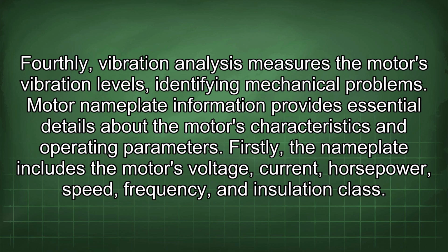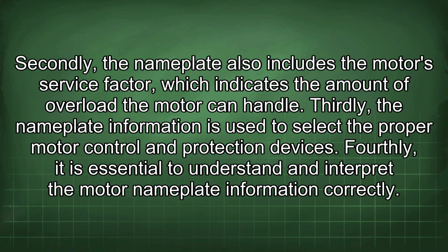Motor nameplate information provides essential details about the motor's characteristics and operating parameters. Firstly, the nameplate includes the motor's voltage, current, horsepower, speed, frequency, and insulation class. Secondly, the nameplate also includes the motor's service factor, which indicates the amount of overload the motor can handle. Thirdly, the nameplate information is used to select the proper motor control and protection devices. Fourthly, it is essential to understand and interpret the motor nameplate information correctly.